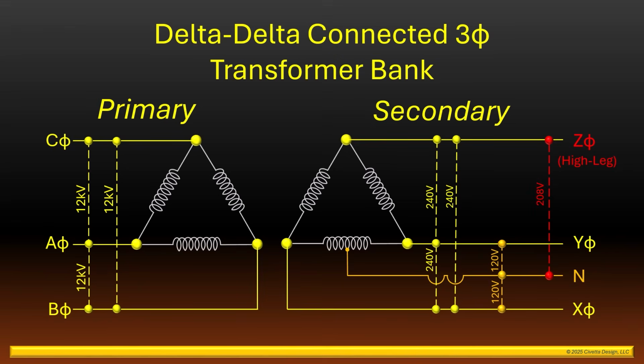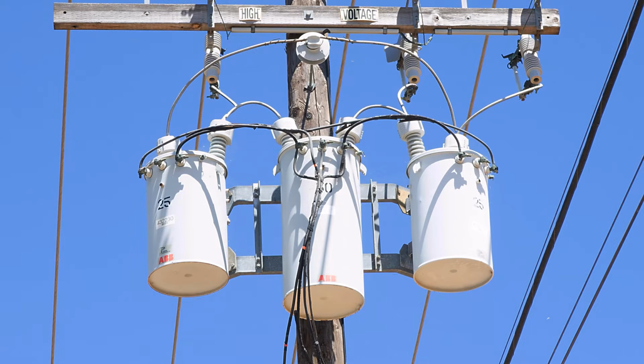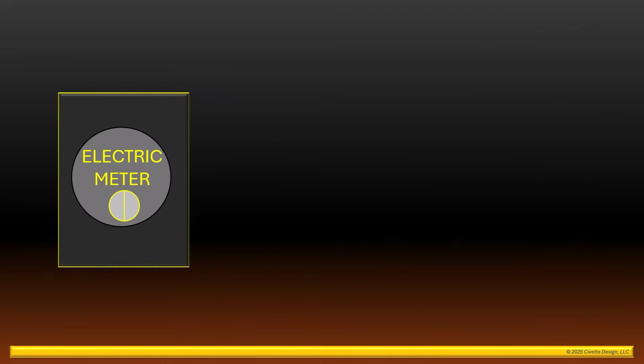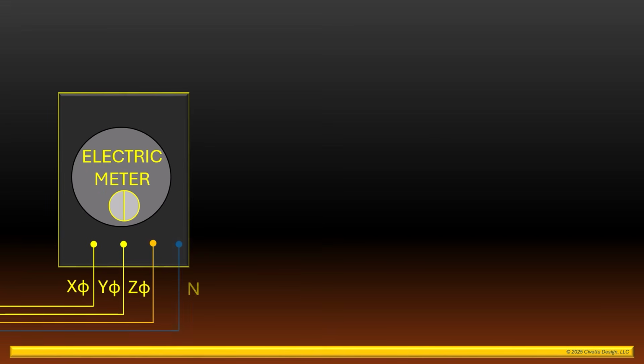It provides a three-phase, four-wire service consisting of an X phase, a Y phase, a Z phase, also known as the high leg, and a neutral conductor. The four-wire service conductors are shown here. These are the conductors that extend to and are connected to the customer's meter panel. The three-phase four-wire service is connected to the customer's meter panel: X phase, Y phase, the high leg, and the neutral.